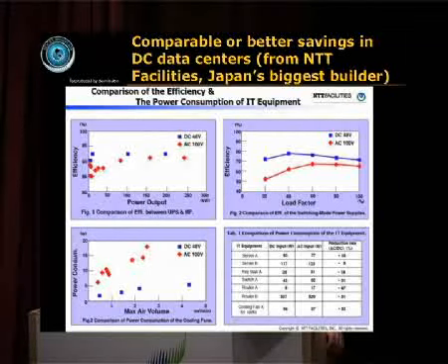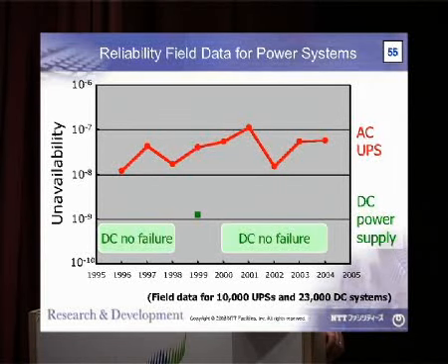It obviously depends on the equipment and the duty. And now the real stunner, look at the unavailability. Over an order of magnitude improvement for DC versus AC uninterruptible power supply. A case closed as far as I'm concerned, because the economics are great. And what you pay so much for in a data center is uptime. This is reflecting field data for 10,000 uninterruptible power supplies and 23,000 DC systems. They've never had a failure in a DC system. I think that's pretty convincing.